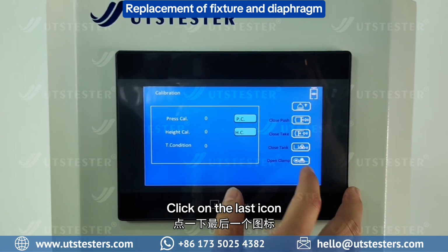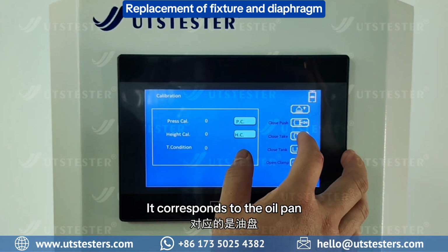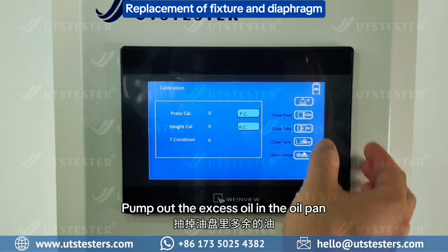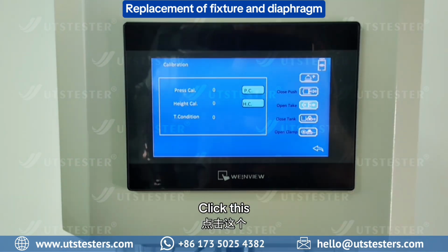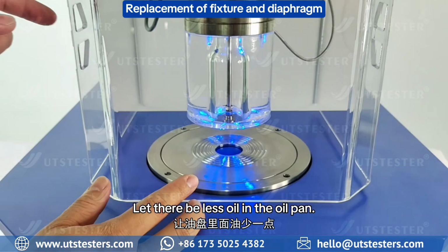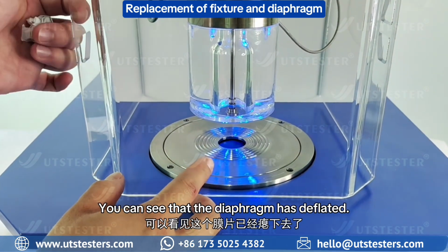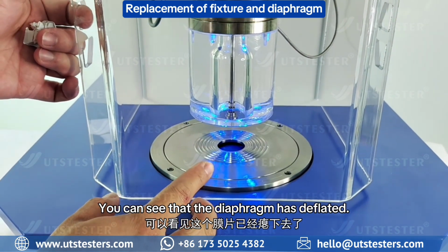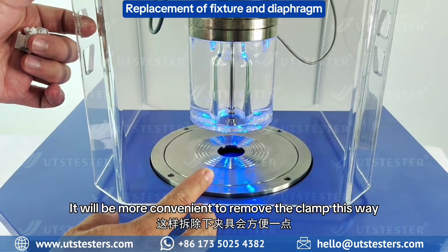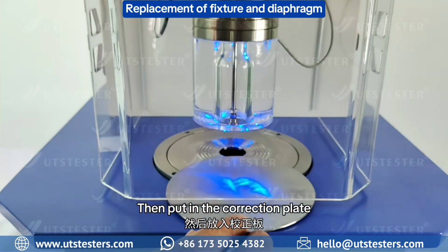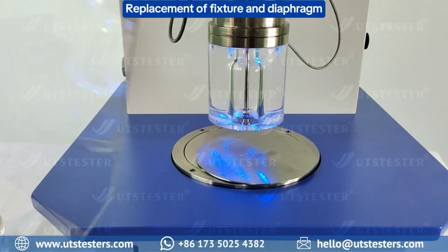Click on the last icon. It corresponds to the oil pan. Pump out the excess oil in the oil pan. Click this. Let there be less oil in the oil pan. You can see that the diaphragm has deflated. It will be more convenient to remove the clamp this way. Then put in the correction plate.